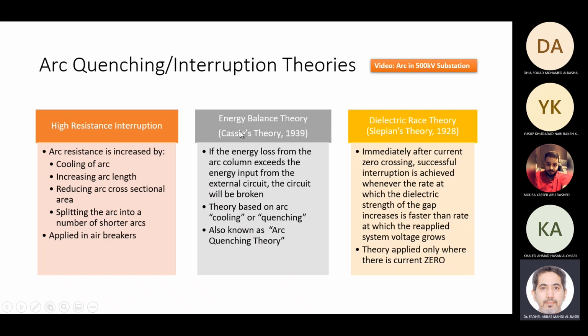And there is another theory for extinguishing arcs, based on the energy balance. If the energy loss from the arc, when the arc is cooled by the cooling medium, is greater than the heat generated from the fault current, then they will be able to extinguish the arc. This is called the arc quenching theory, which is based on heat energy balance.